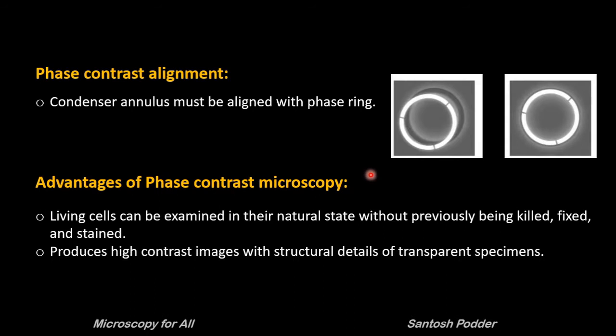Always check the phase contrast alignment before you start. The dark ring of the phase plate must be perfectly aligned with the bright ring of light from the condenser annulus, and the adjustment can be made using two condenser centering screws. Using phase contrast microscopy, living cells can be examined in their natural state without killing or fixing, and it can provide high contrast images with structural details of transparent specimens.